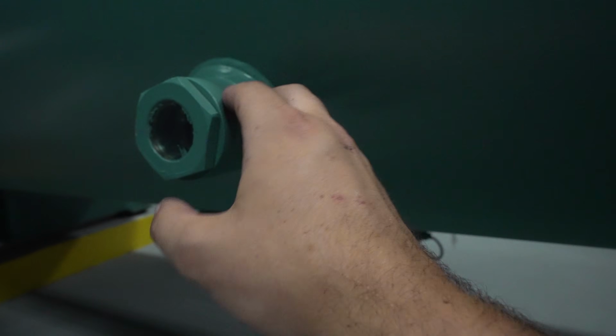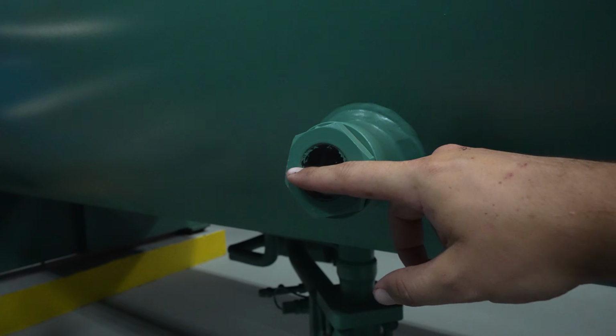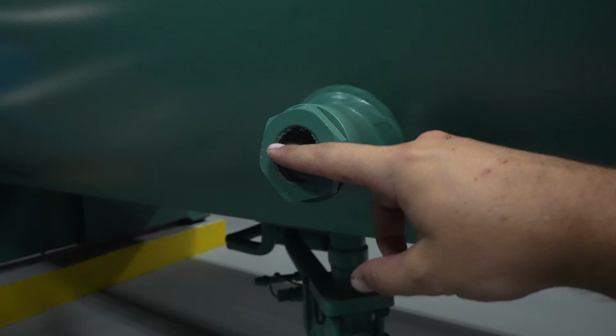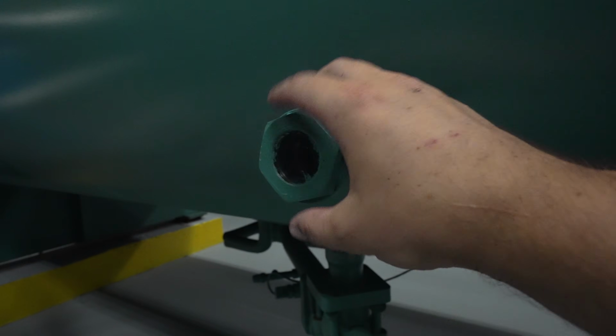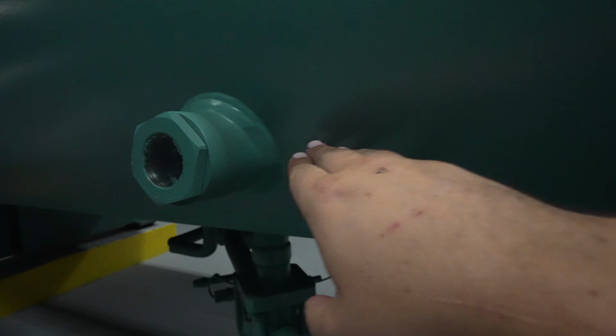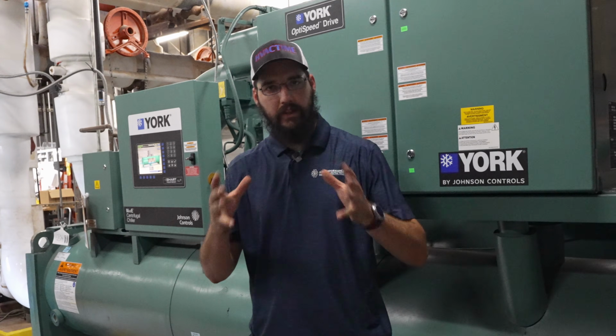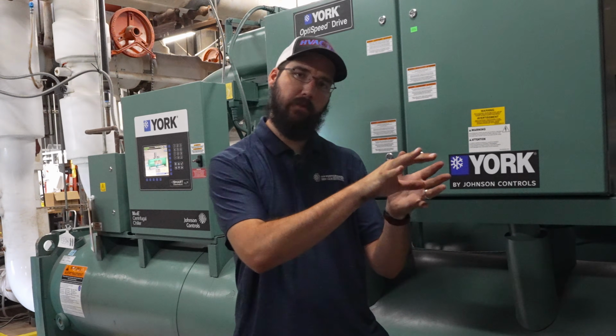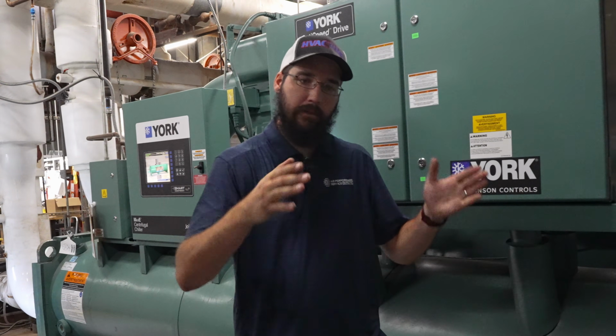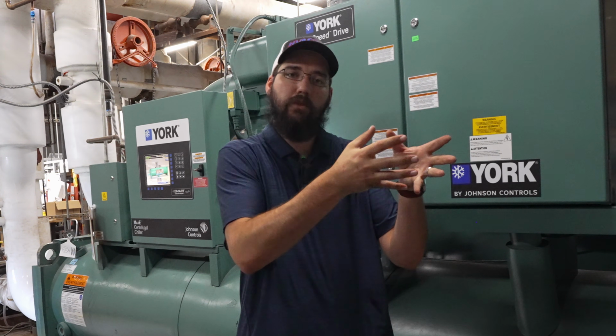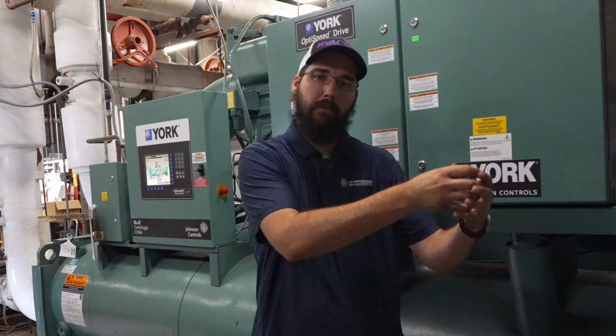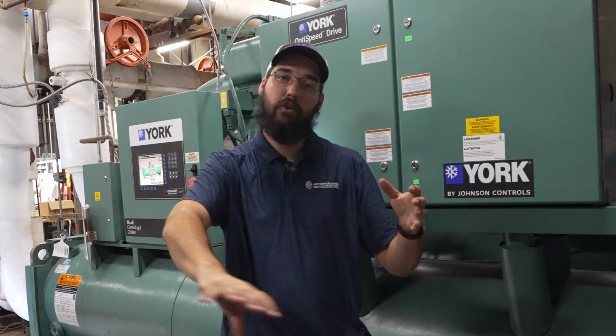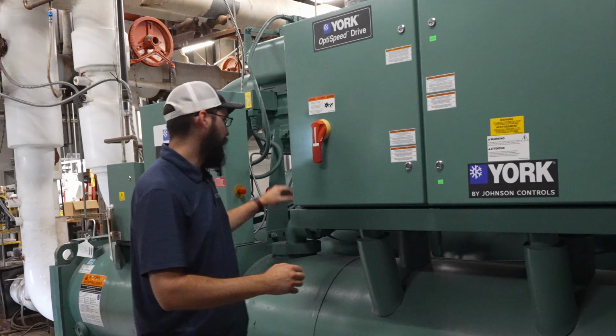Because these aren't machined, these are not perfect units of measure. So just going based off of sight glass level is not sufficient, because it is going to change and vary depending on each machine you're working on. The subcooler bundle is housed inside of a stainless steel shroud, and it runs the whole length of the barrel, all the way down from one end to the other. Inside of that housing, the tubes are just in racks, a metal rack where the subcooler tubes run through. The refrigerant comes down and underneath and swirls up into that rack assembly, cools, and in the middle of the condenser is where we have our liquid drain, which goes to our metering valve on top of the evaporator, which is sitting right over here.